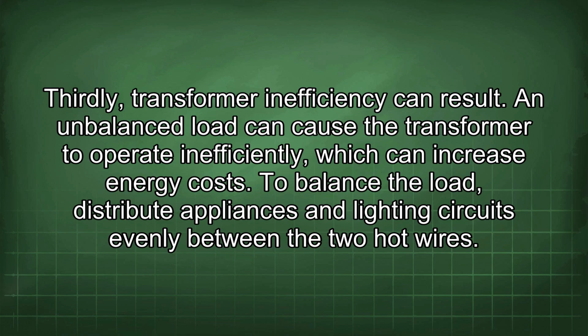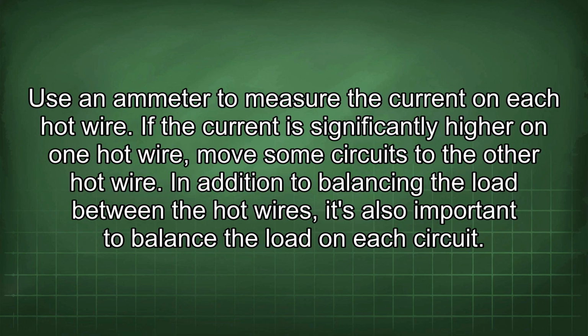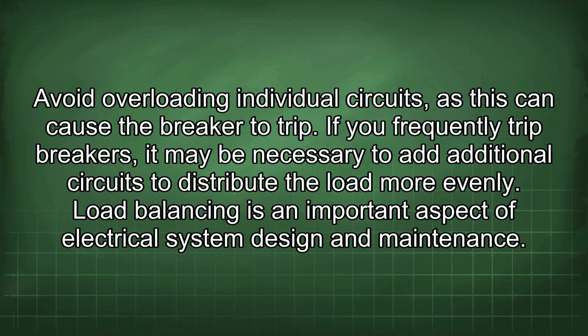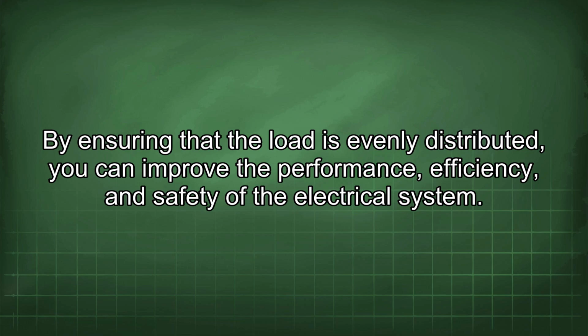To balance the load, distribute appliances and lighting circuits evenly between the two hot wires. Use an ammeter to measure the current on each hot wire. If the current is significantly higher on one hot wire, move some circuits to the other hot wire. In addition to balancing the load between the hot wires, it's also important to balance the load on each circuit. Avoid overloading individual circuits, as this can cause the breaker to trip. If you frequently trip breakers, it may be necessary to add additional circuits to distribute the load more evenly. Load balancing is an important aspect of electrical system design and maintenance. By ensuring that the load is evenly distributed, you can improve the performance, efficiency, and safety of the electrical system.